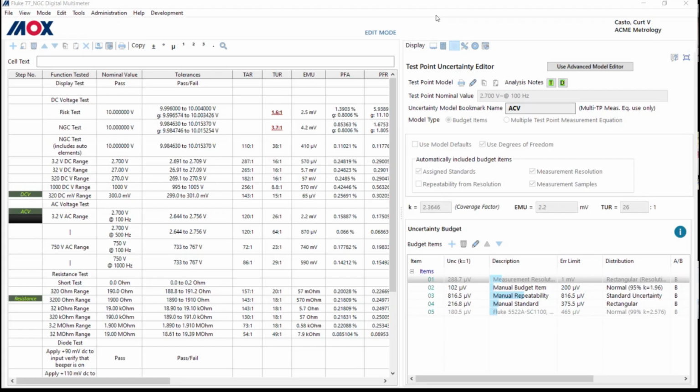And you actually still have the approval process. This is what happens a lot. The technicians will create the data sheet and then send it to the metrology engineer, or whoever the person or persons are that are authorized to approve them for that lab. Typically the senior techs in the lab or a metrology engineer will review them and say, okay, this all looks right, I'm going to approve it. And then it can be used for calibrations.